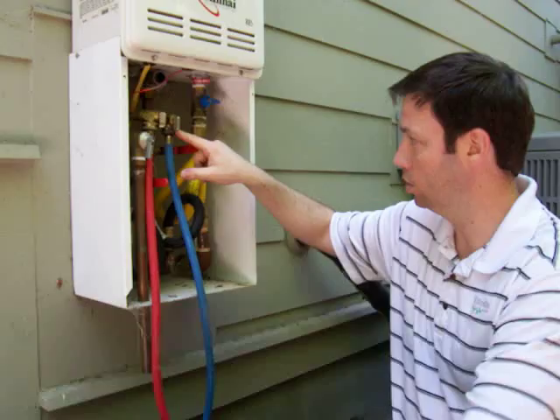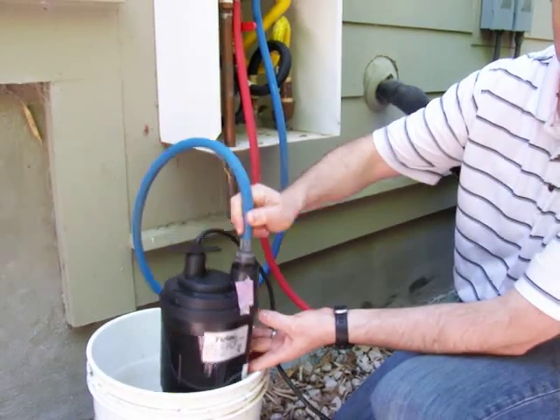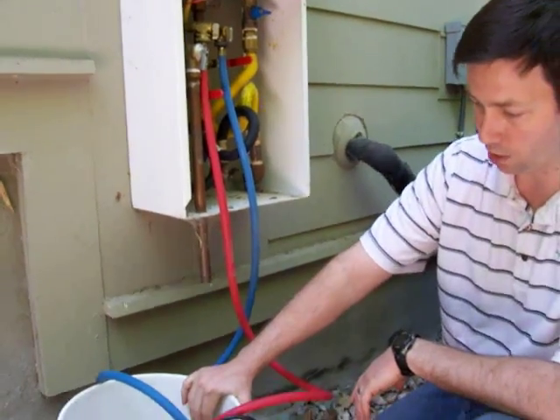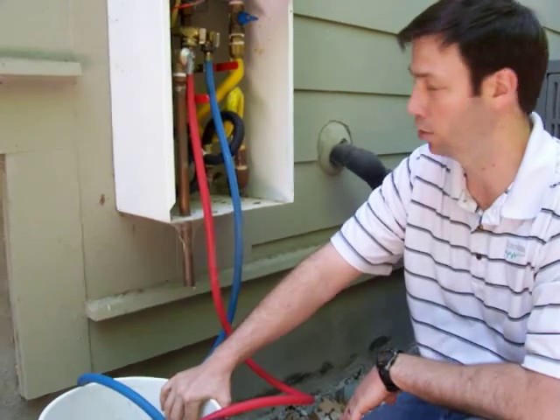Then we're going to hook up a hose to the inlet side and you can see that runs into a sump pump right here. This is just a one-sixth horsepower submersible sump pump. We used a five gallon bucket and we're using just off-the-shelf white vinegar — somewhere between two and three gallons to flush a water heater.